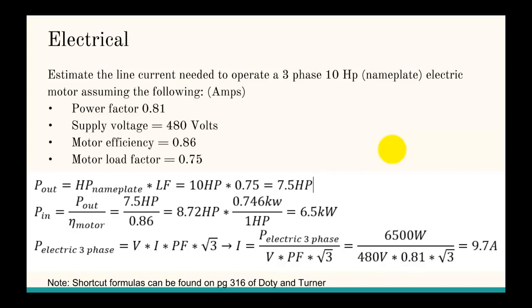So, in this case, we're estimating the line current, or the amps, needed to operate a three-phase 10 horsepower nameplate electric motor. We're going to assume the following: a power factor of 0.81, a supply voltage of 480 volts, a motor efficiency of 0.86, and a motor load factor of 0.75.